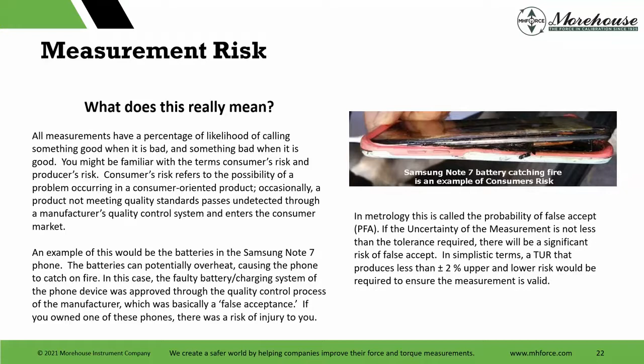But when we look at metrology, we're calling these PFAs and PFRs, probability of false accept and probability of false reject. That means, hey, as a calibration service provider, we're rejecting something that might actually be good. That falls on us, right? We typically adjust it and send it back out to the customer. Probability of false accept means we said something was good that actually has a really high risk. And when that customer then uses it, they've built up a global consumer's risk, and every instrument they calibrate and every instrument that instrument calibrates is subject to additional error, and it might mean the difference between something catastrophic happening and something not.